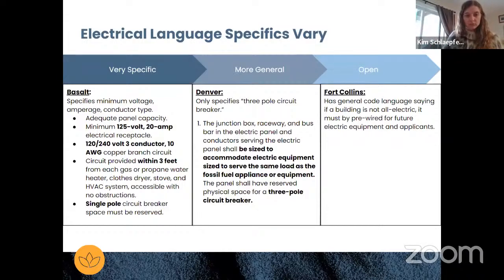Tim, you're muted still. Sorry about that - that was a good point. I was keyed in just on the rooftop equipment, but absolutely there are gas-fired water heaters, different units going in. We also have the discussion on commercial kitchens, which are typically gas-fired, and I'm assuming we'll get an exception there, like I've seen even in communities that have done all-electrification. So with all that being said, maybe instead of specifying a 3-pole circuit breaker, we come up with more generic language about adequate breaker size and physical space for a breaker that would adequately handle whatever piece of equipment it is.